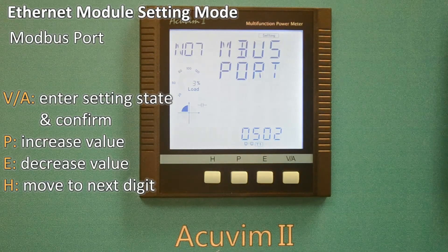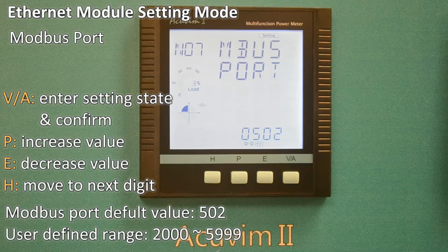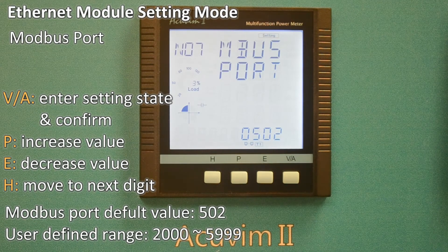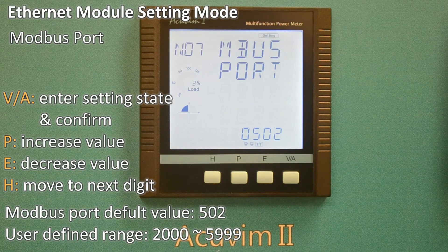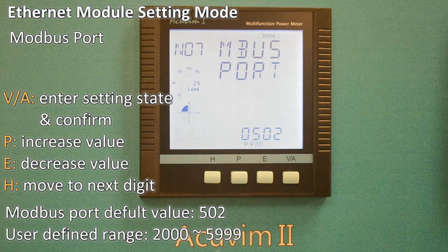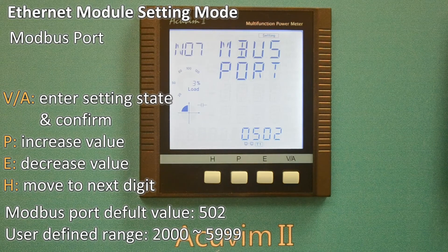You can set the Modbus port using the same method. The Modbus TCP port default value is 502, and the user defined range of ports is 2000 to 5999. If the port number entered is not in the correct range, the set port will return to the default value.